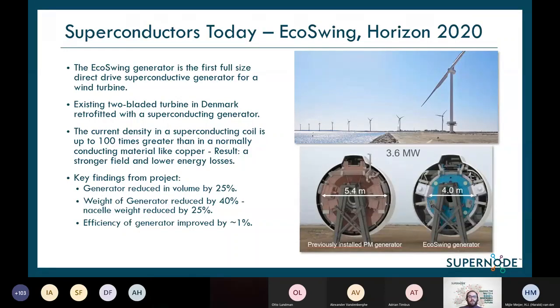The EcoSwing project was a Horizon project built a few years ago, which took an existing two-bladed demonstration turbine and retrofitted the generator with a superconducting alternative. The benefits were vast, due to the superconducting coils' ability to achieve a much higher current density than the conventional generator before it. This, along with improved magnetic fields in the generator, resulted in the generator's volume being reduced by approximately 25% and its weight decreasing by 40%, leading to a net 25% decrease in nacelle weight overall.